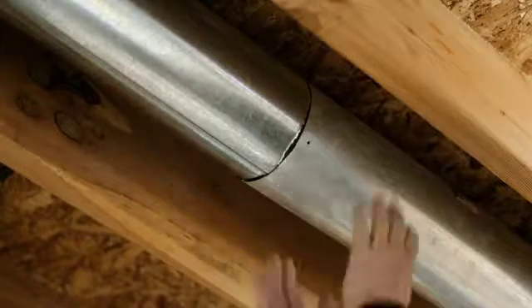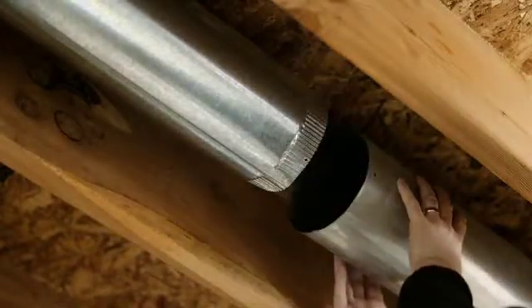For zone control, start by determining the location of the damper and remove a 6-inch section of duct at an existing joint. Slide the damper unit in place so that you can easily access the electric terminal block and that the ends are inserted at least one inch.